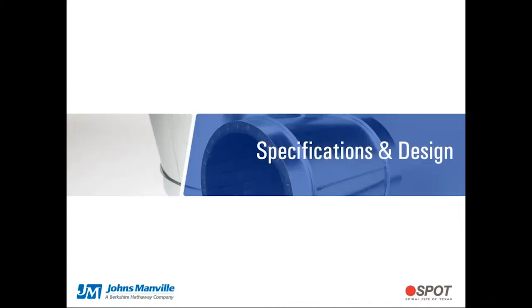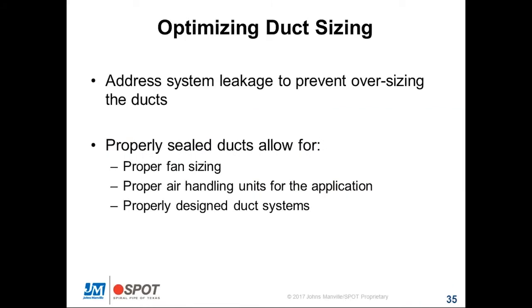Optimizing duct sizing. System leakage to prevent oversizing of ducts. If the duct is properly sealed, then the designers are not having to oversize that duct to allow for that leakage. I think we're going to see more and more jobs on a daily basis requiring that all these ducts be sealed, even the low pressure systems.